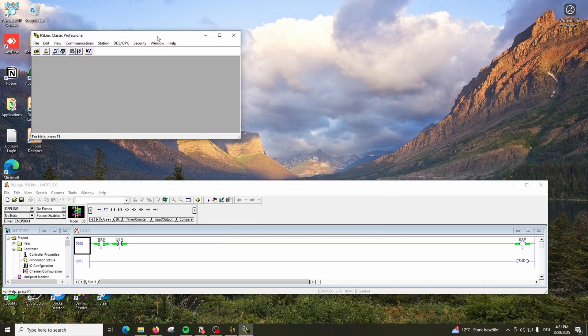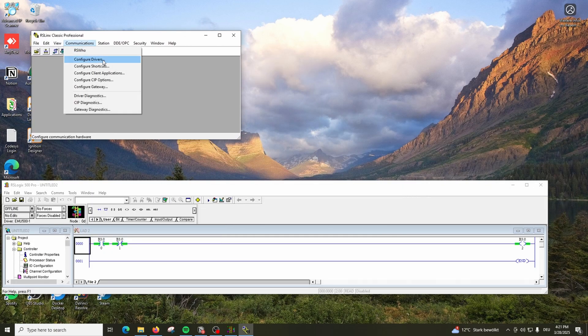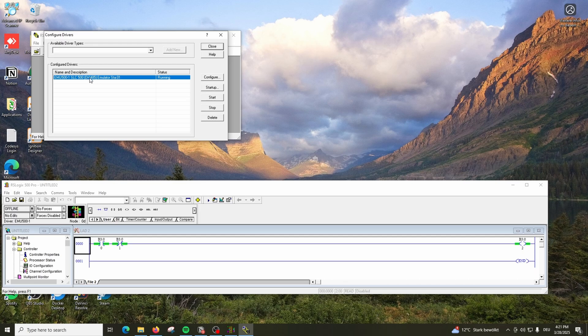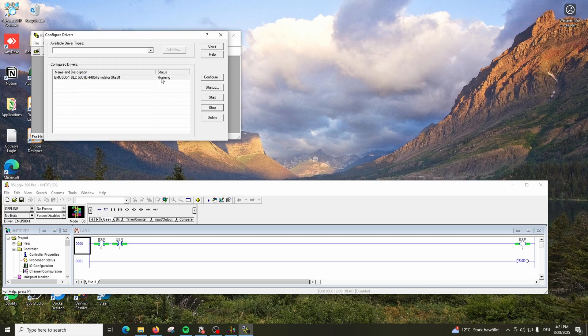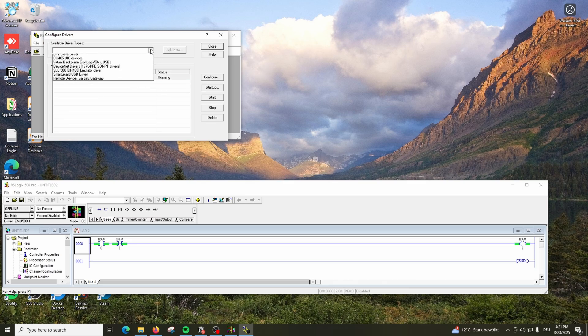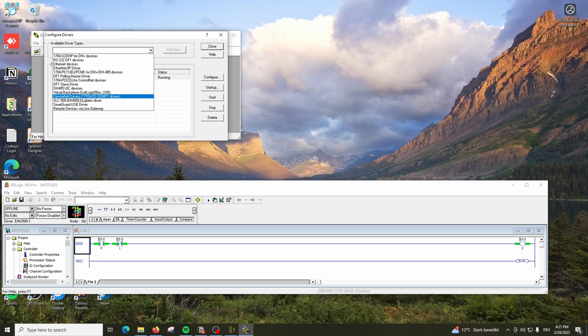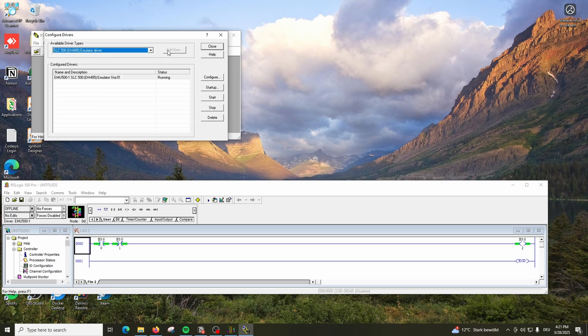Now open RSLinx Classic. There you have to make sure you go to Drivers and your driver is running. If you don't have this driver, go here and select SLC 500 and click Add. In my case it's faded because it's already there. Click Add and define the station number - I put station number one.